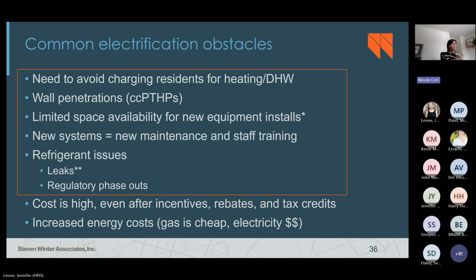We don't have excessive wall penetrations, which can be a concern with PTHPs. And then space availability. When we're using hydronic distribution at low temperature, we're using water piping, and it doesn't need to be boxed out like A2L refrigerant piping does. And if we keep it below that 105°F temperature, it doesn't even need to be insulated. So that leaves us with a really small chase footprint that's required.